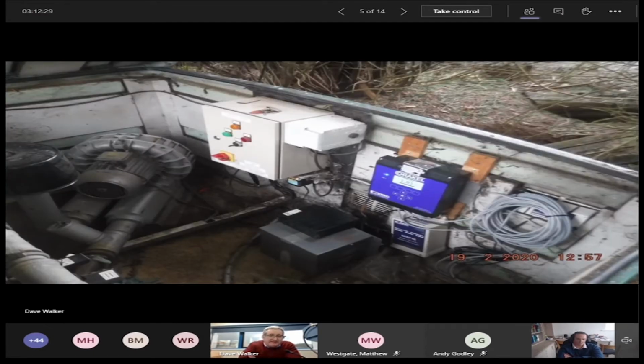So particularly in installation, you've got a great big power pump at the left-hand side there, the white box, switchgear with a solenoid at the bottom. When that solenoid kicks in, that gives out quite a lot of EMF, and it can be picked up on instrumentation. Interesting in this case, it's not actually the instrument side of it, it's the earth supply transmitting that noise down to the receive circuit, and then the receive circuit amplifying the noise as it transmits that high power voltage peak when that solenoid kicks in and out. And it only happens every now and again.